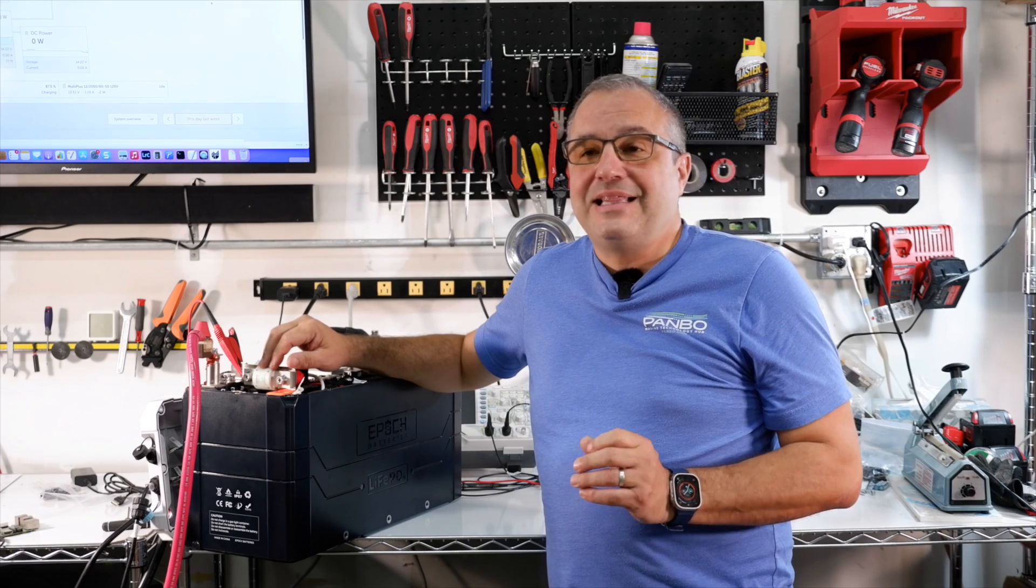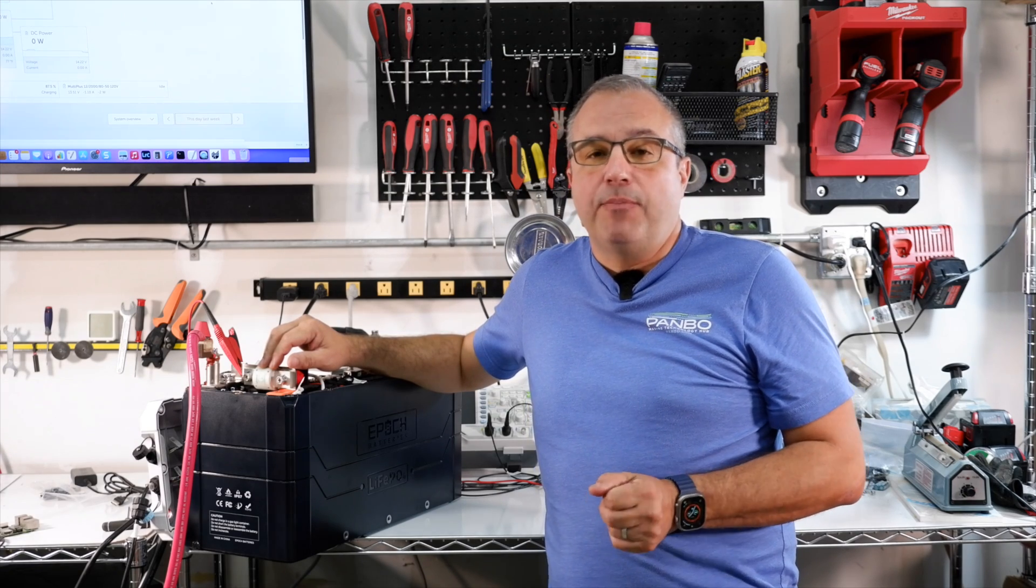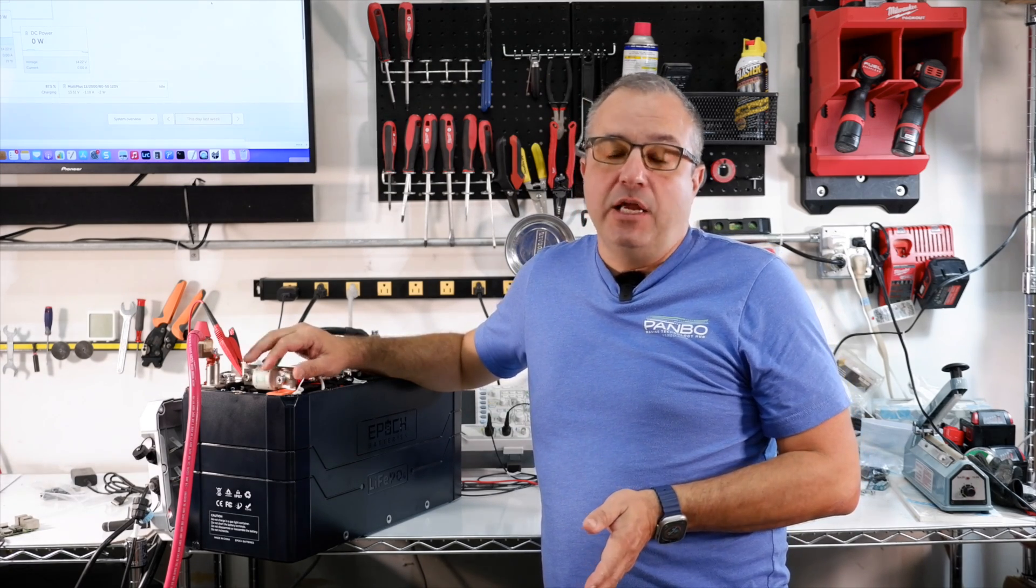The reason for that is the Class T has an amp interrupt rating of 20,000 amps. What that means is that even with a load of 20,000 amps, the fuse will blow and it will blow into an open position. Fuses with a smaller AIC or amp interrupt capability rating may weld themselves shut under a greater load. That would obviously be very dangerous because now your over current protection has failed to open and has in fact welded itself closed.